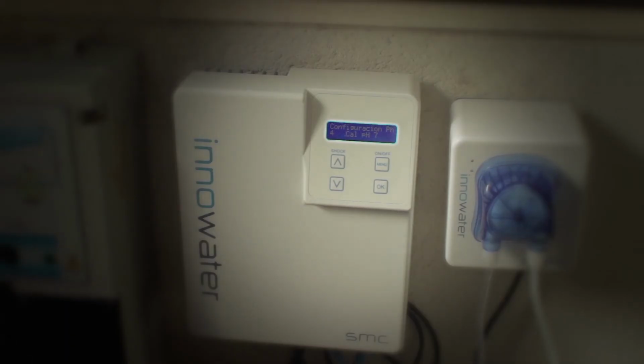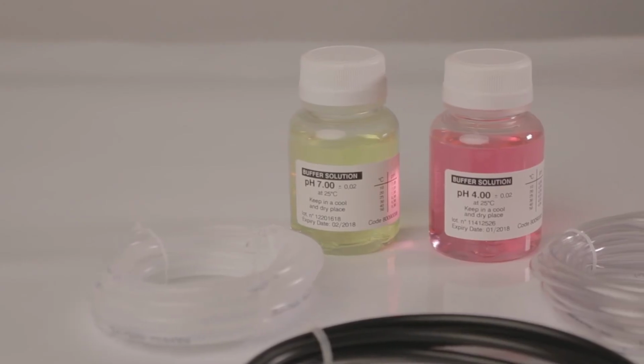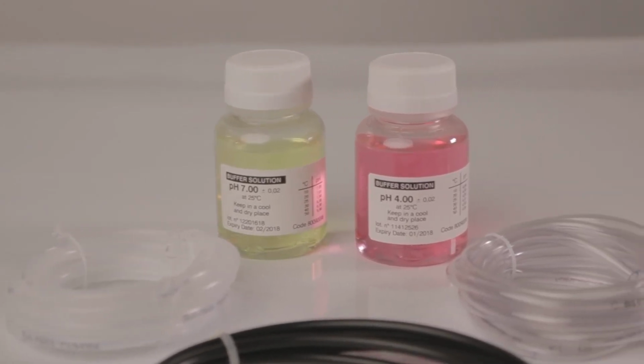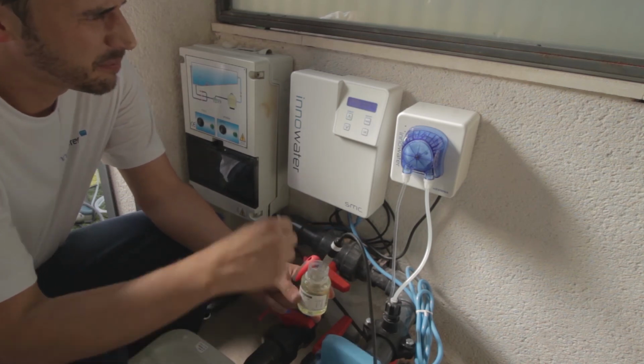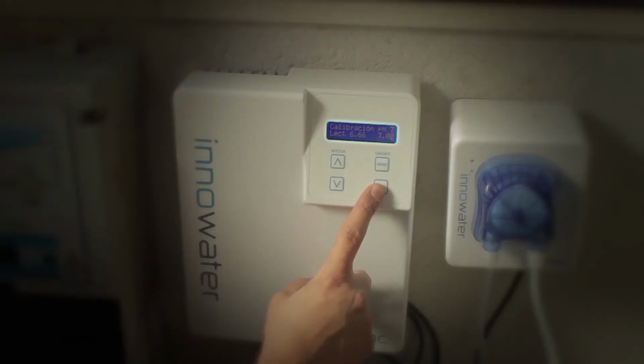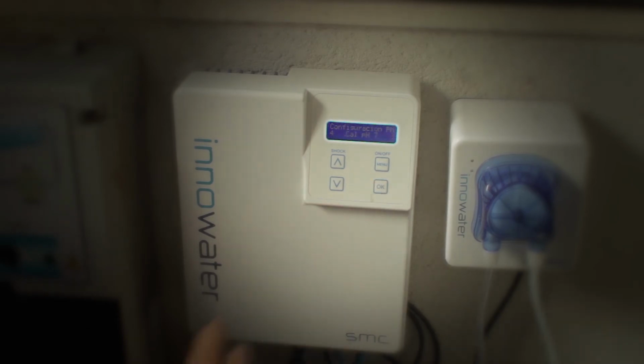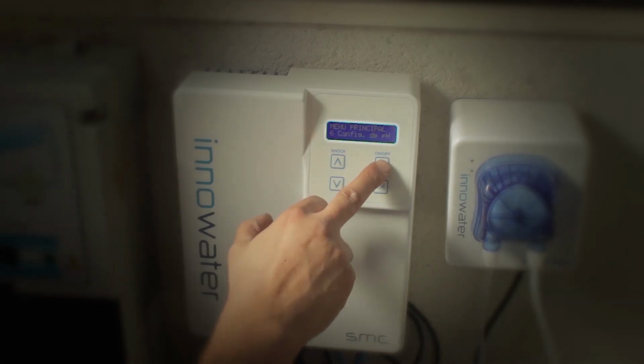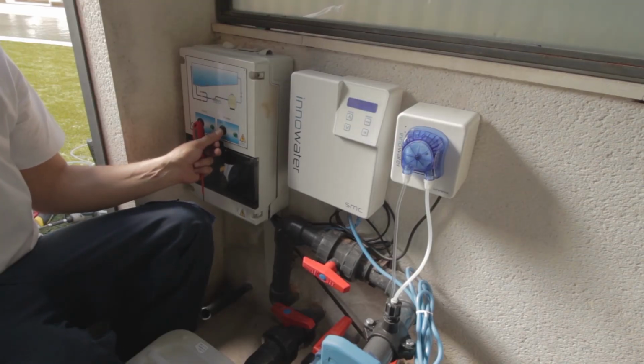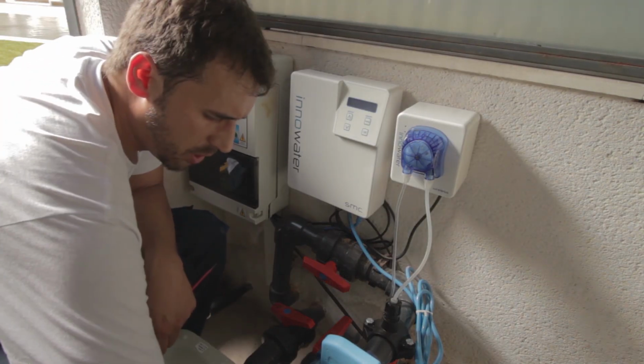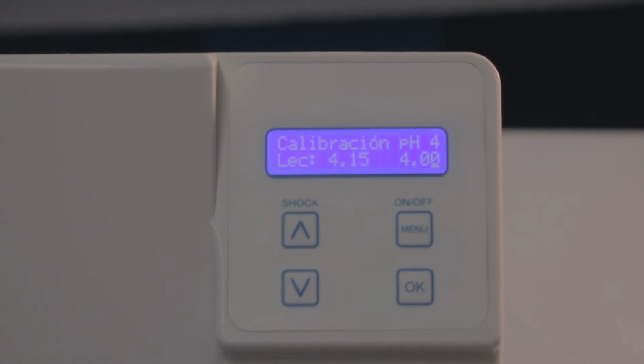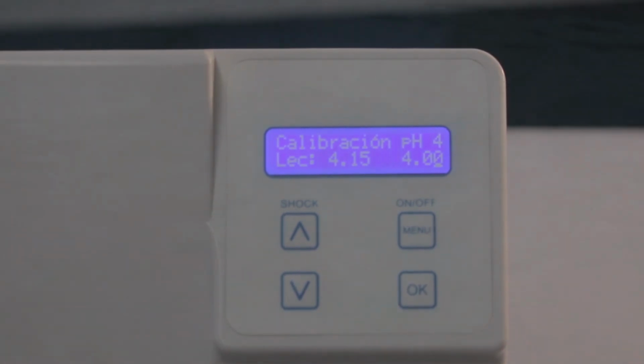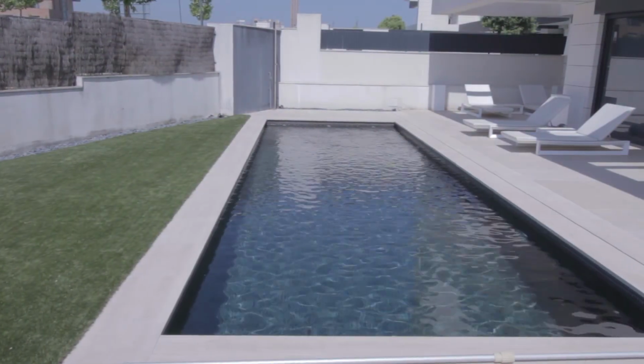Repeat this procedure for point 4, calibration pH 7. Take pH 7 liquid, pour it into the probe, which should give you an approximate reading of 7. Check the reading, 7. After these 2 steps, the probe is calibrated. You can now leave the menu. Turn off the engine and place the probe. You can also calibrate before the whole installation process using the memory. Once we have completed this step, the installation is over.